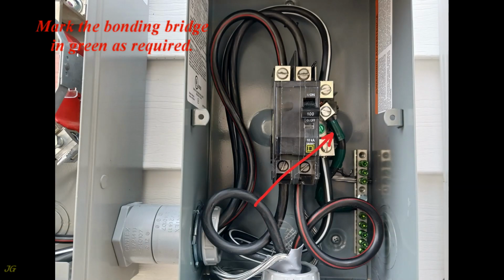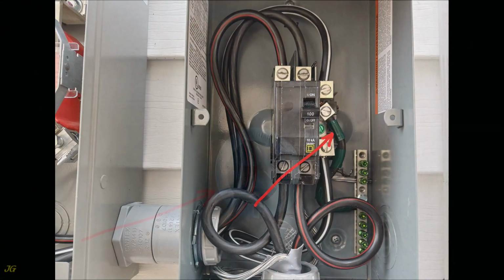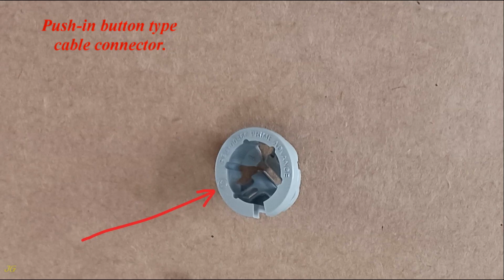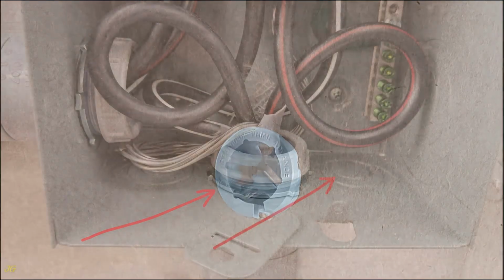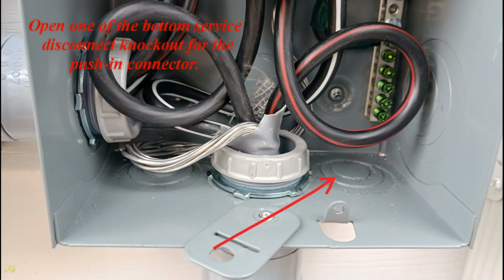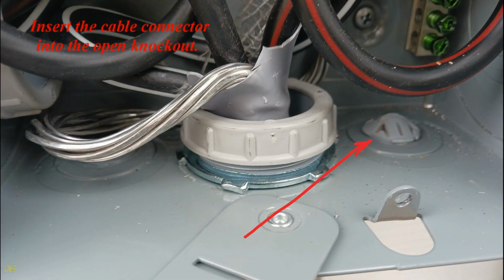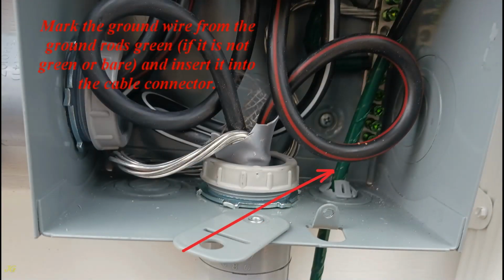Mark the bonding bridge in green as required. Push-in button type cable connector. Open one of the bottom service disconnect knockouts for the push-in connector. Insert the cable connector into the open knockout. Mark the ground wire from the ground rods green, if it is not green or bare, and insert it into the cable connector.